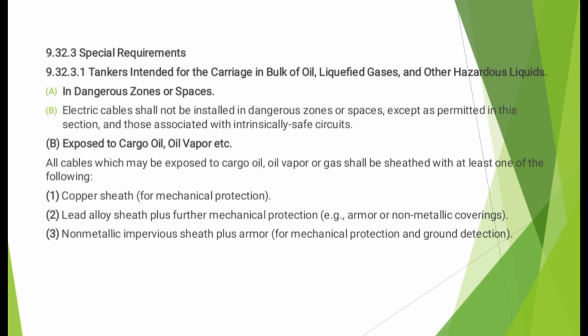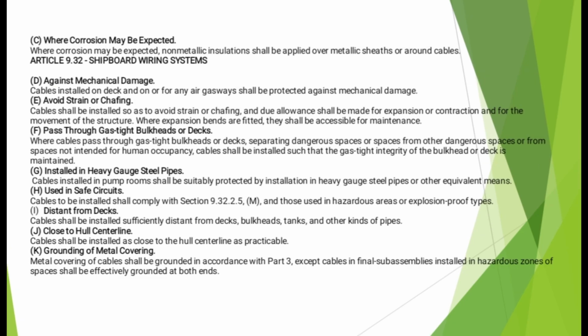Exposed to cargo oil, oil vapor, etc. All cables which may be exposed to cargo oil or oil vapor gas shall be sheathed with at least one of the following. 1. Copper sheath for mechanical protection. 2. Lead alloy sheath plus further mechanical protection. 3. Non-metallic impervious sheath plus armor. Where corrosion may be expected, non-metallic insulation shall be applied over metallic sheaths and around cables. Against mechanical damage, cables installed on deck and on or for any air gasways shall be protected against mechanical damage.